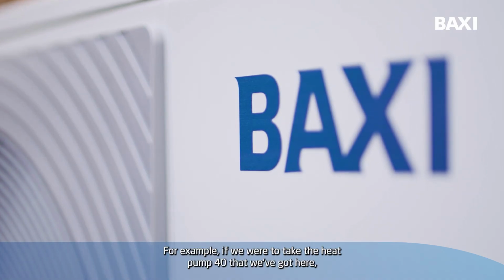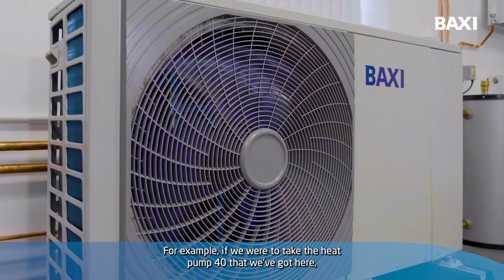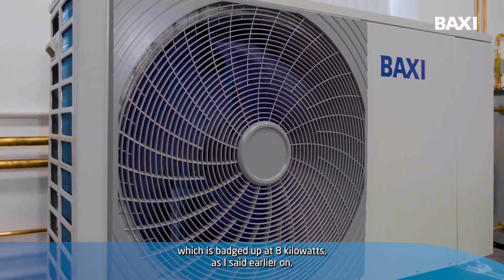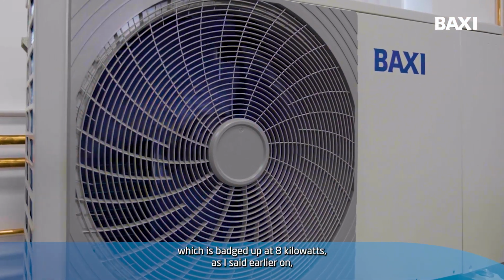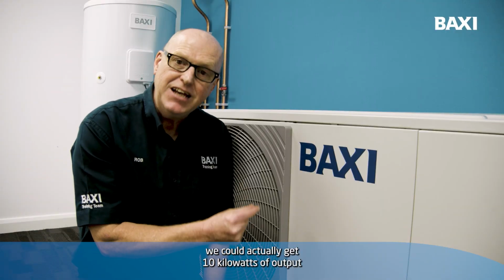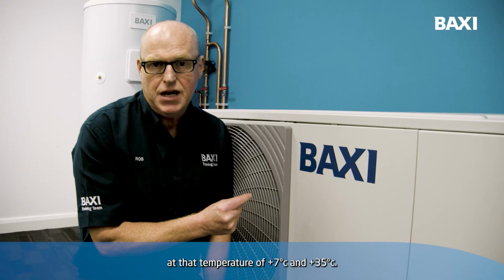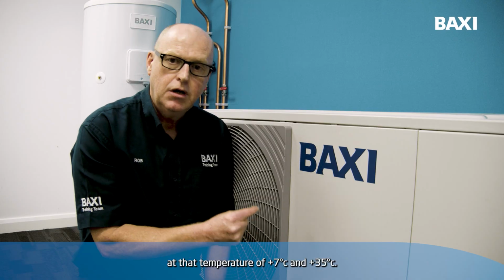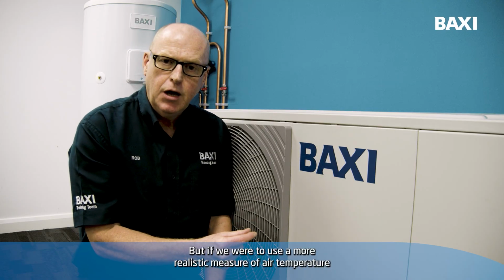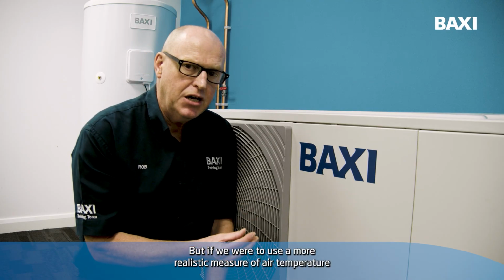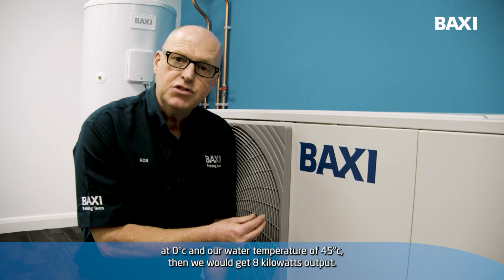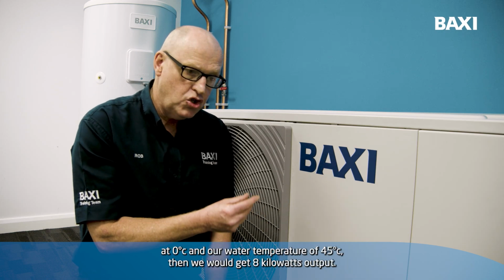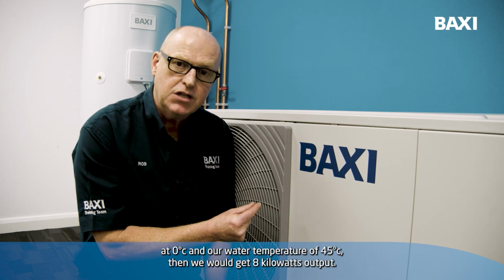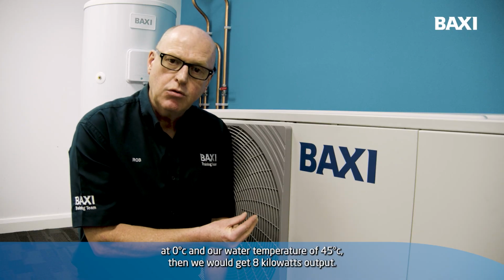For example, if we were to take the heat pump 40 that we've got here, which is badged up at 8 kilowatts, as I said earlier on, we could actually get 10 kilowatts of output at that temperature of +7 and +35. But if we were to use a more realistic measure of air temperature at 0 and our water temperature of 45 degrees C, then we would get 8 kilowatts output.